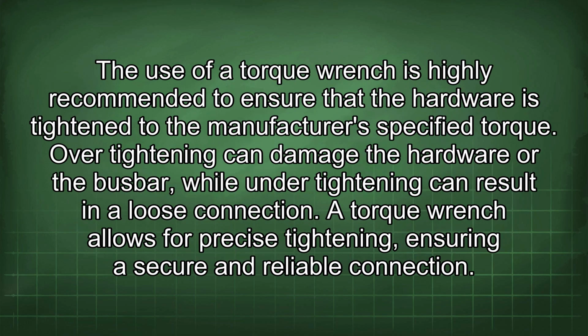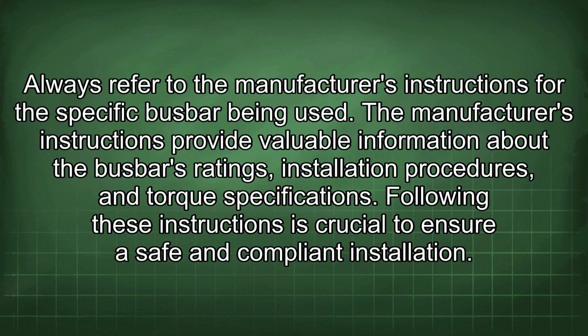The use of a torque wrench is highly recommended to ensure that the hardware is tightened to the manufacturer's specified torque. Over-tightening can damage the hardware or the busbar, while under-tightening can result in a loose connection. A torque wrench allows for precise tightening, ensuring a secure and reliable connection. Always refer to the manufacturer's instructions for the specific busbar being used. The manufacturer's instructions provide valuable information about the busbar's ratings, installation procedures, and torque specifications. Following these instructions is crucial to ensure safe and compliant installation.